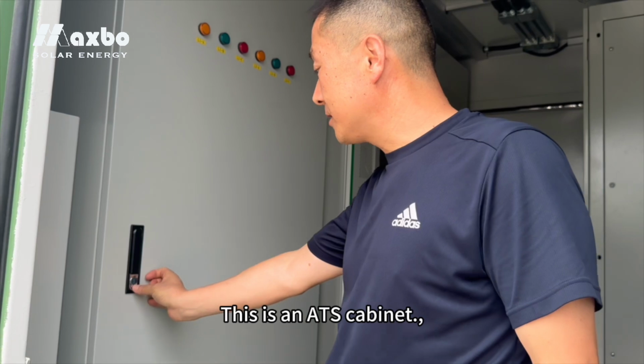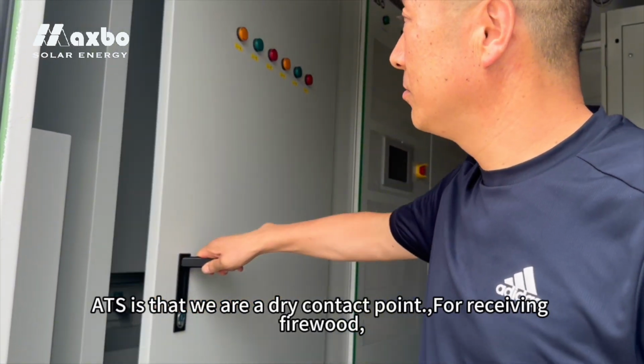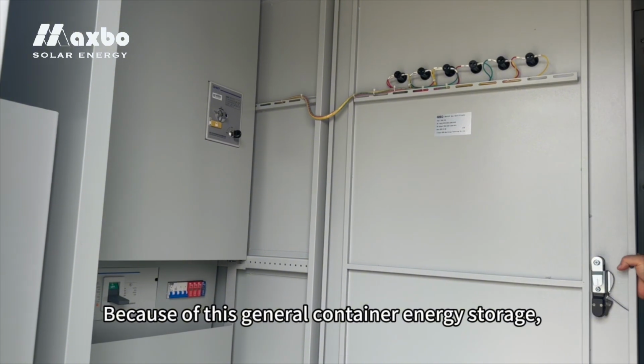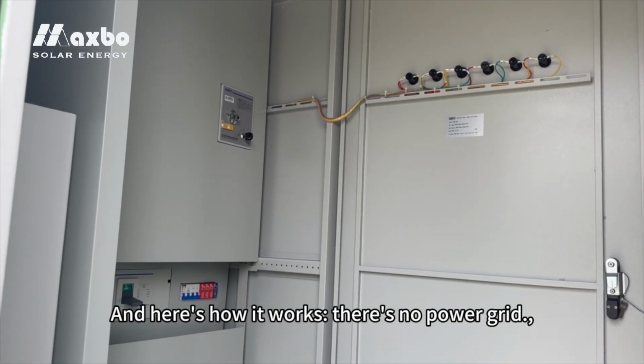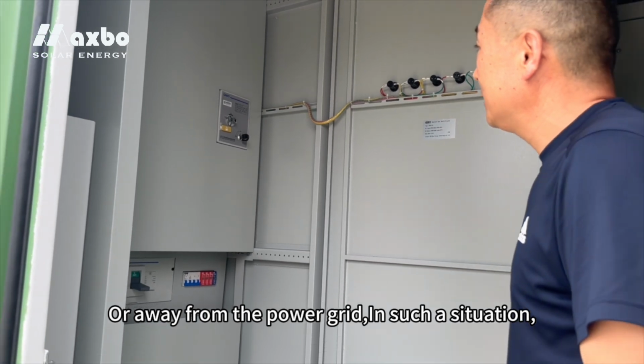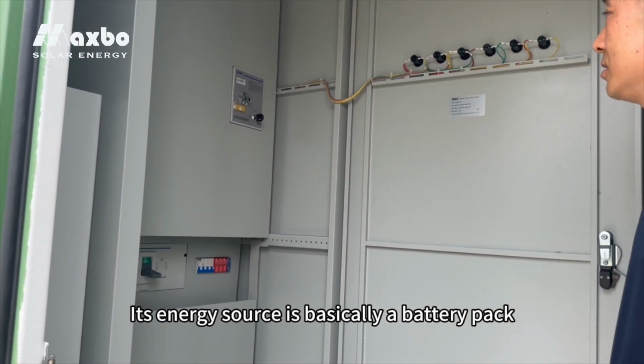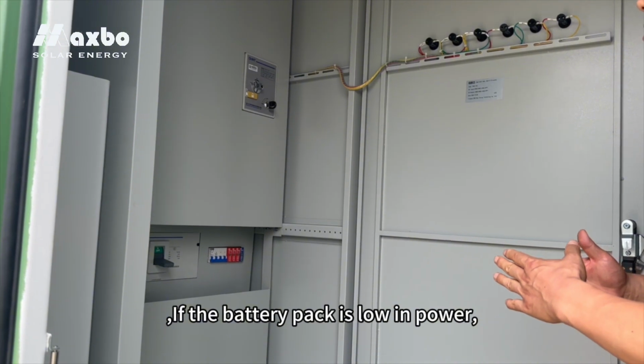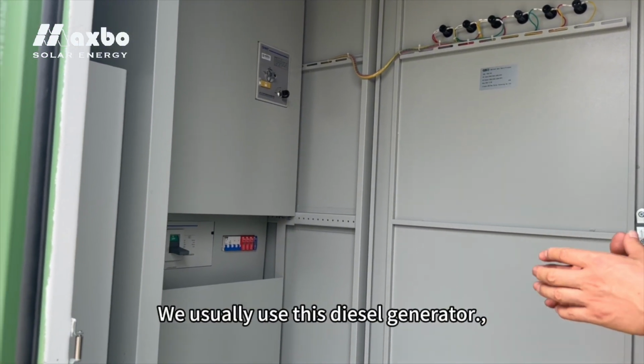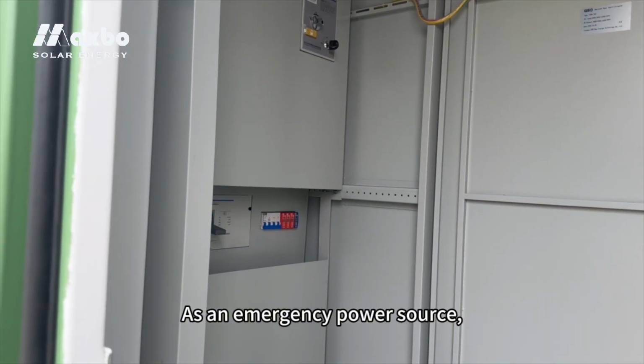This is an ATS cabinet. ATS is a dry contact point for receiving the start signal, because of this general container energy storage. Here's how it works. If there's no power grid, or we are away from the power grid, its energy source is basically the battery pack. If the battery pack is low on power, we usually use this diesel generator as an emergency power source.